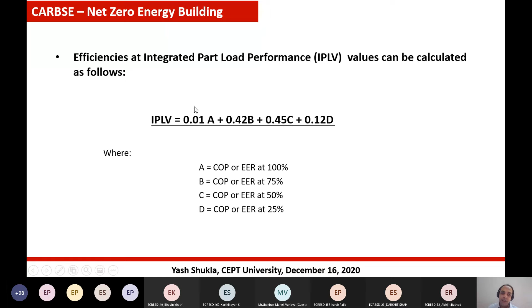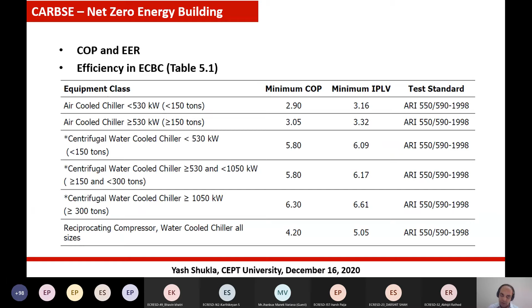So that's why this metric is derived, to give you an indication that you can put all of this together and get a value that is more realistic of what you will see in the real world, right? And you can see that these values are even higher than COP values. So it shows that the part load performance of these units is expected to be better at certain capacities. So you should not only check the COP of a unit, but also the IPLV, or the part load performance of the unit, when selecting your air conditioning systems. This is very important for the net zero energy design.